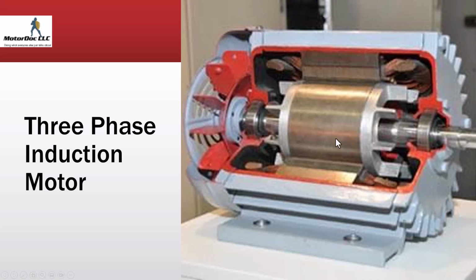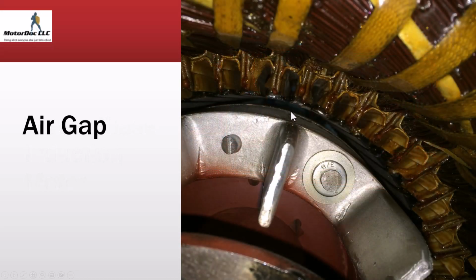Now, this is a common induction machine. There are new types with different variations of the core. Those can just as easily be tested because our actual transducer is in here, or this portion between the rotor and the stator. The air gap in the machine, that is the transducer, just like a vibration transducer for electrical signature analysis, and as a matter of fact has much the same impact, except we're detecting variations in that air gap both from a radial movement but also a torsional movement, meaning that defects throughout the system have to drive through this, and any type of motion of this rotor inside here, you end up with an unbalanced magnetic pull, and that causes variations in the current as well.